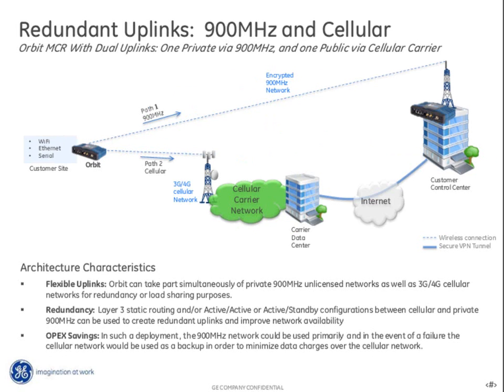Another model, which becomes more important in a lot of cases, is to use private communications such as 900 megahertz unlicensed, or even narrowband, which we're releasing in a month or so. These would be the primary path for communications, a private network owned by the utilities, and the backup path would be cellular. One main reason to do this is to save costs on cellular, especially if you're running multiple applications downstream including voice over IP, video streaming, in addition to SCADA and protection—cellular becomes very expensive because you're talking about gigabytes per month per location. So you use 900 megahertz as your primary network, and if that fails, you fail over to a cellular carrier.